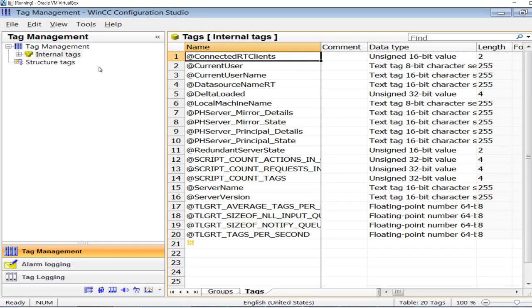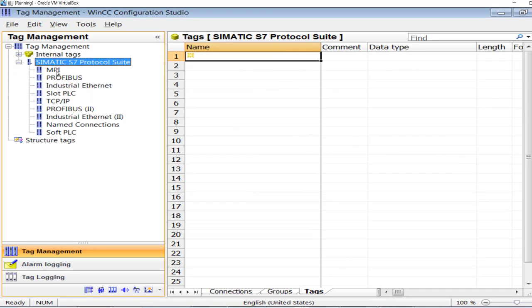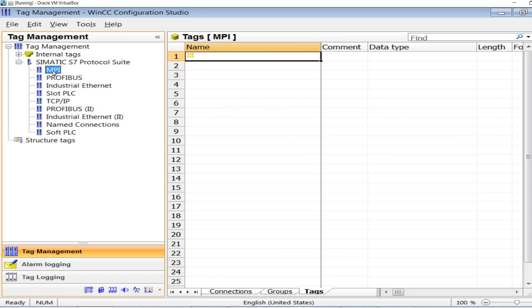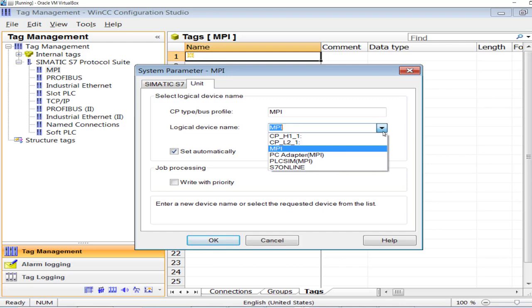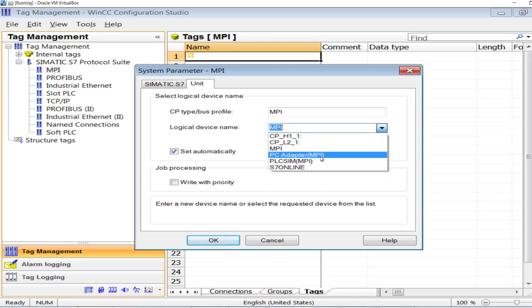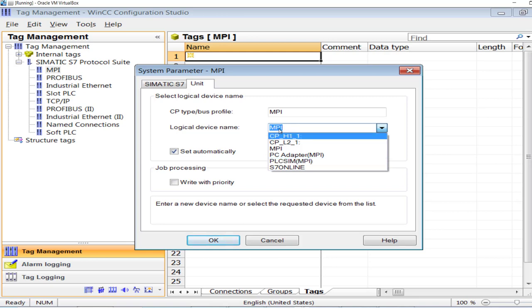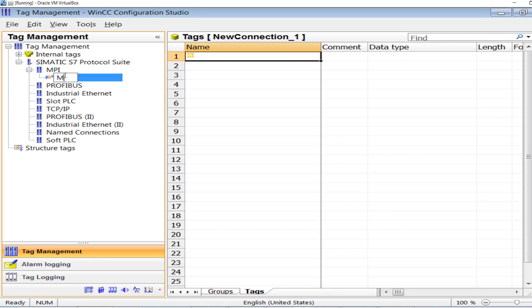Go straight to Tag Management. In Tag Management, add a new driver: SIMATIC S7 Protocol Suite. In the MPI category, first select System Parameters and select MPI. If you have a physical PLC connected to your operator station or PC with WinCC software, select MPI. Since I have a simulator, I will select 'PLC Simulator MPI'. If you have an actual physical PLC, simply select MPI.